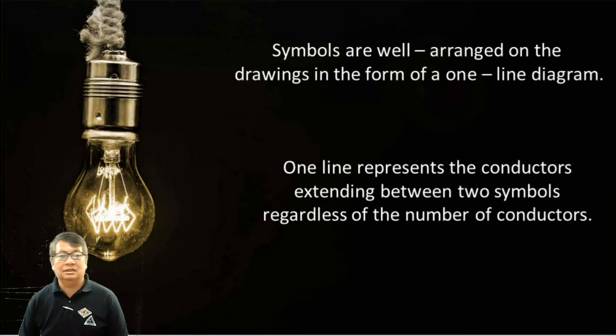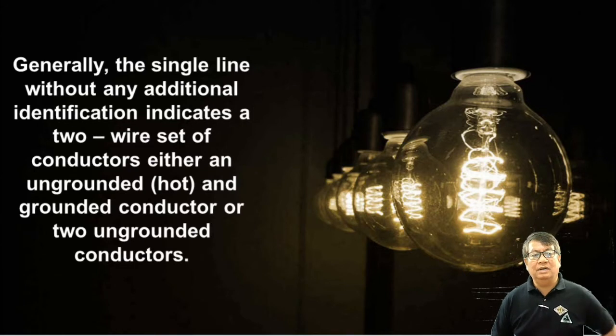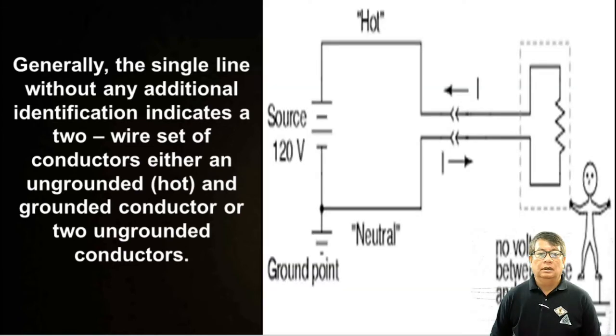One line represents the conductors extending between two symbols regardless of the number of conductors. Generally, a single line without any additional identification indicates a two-wire set of conductors, either one ungrounded hot and one grounded conductor, or two ungrounded conductors. This was just a suggestion. Okay, so ito po yung example ng single line without any additional identification. So we have this example.